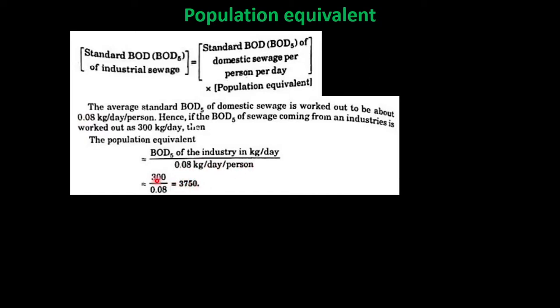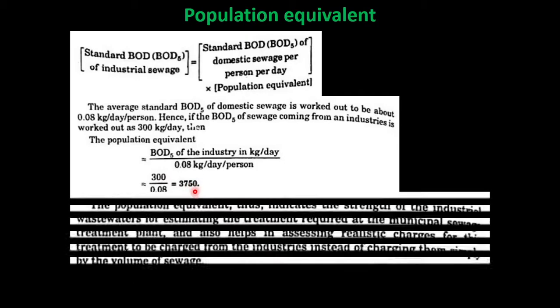For example, 300 divided by 0.08 equals 3,750. This population equivalent indicates the strength of the industrial wastewater for estimating the treatment required at the municipal sewage treatment plant, and helps in assessing realistic charges for treatment from industries rather than charging simply by volume of sewage.